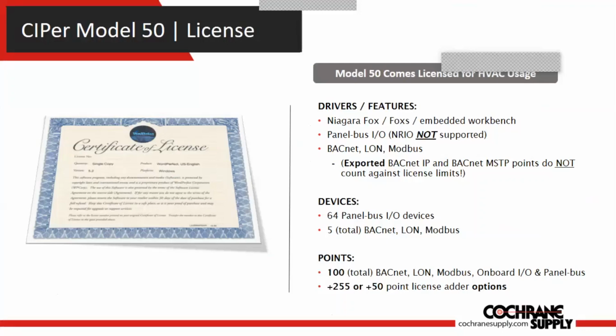In terms of the devices that base license supports, you can add up to 64 panel bus expansion I/O modules. Those are included. You can also add a total of 5 other devices including the CIPer Model 50. So that would count as a device, and then you could have 4 other devices connected to your Model 50 on this base license.